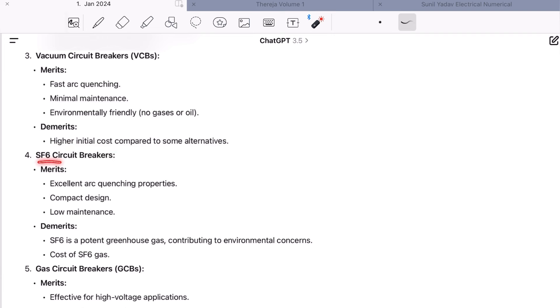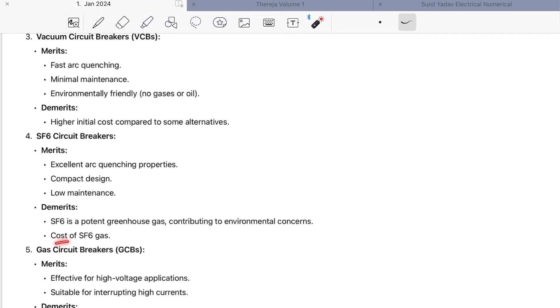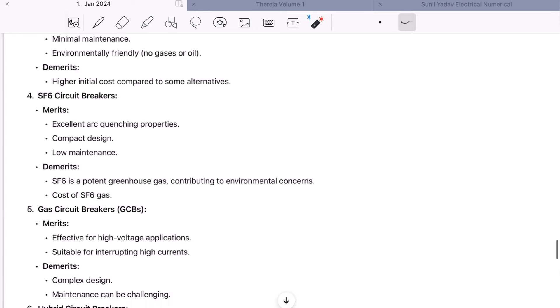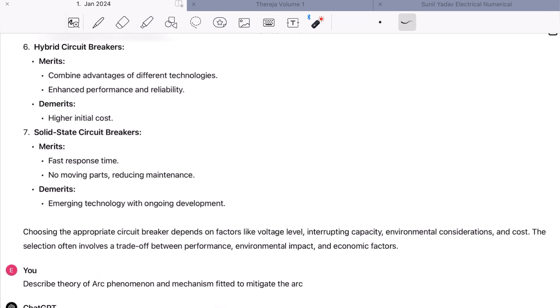Vacuum circuit breaker merits: fast arc quenching, minimum maintenance, and environmentally friendly — no gases or oils. Demerits: higher initial cost. The next type is SF6 circuit breaker. Merit: excellent arc quenching properties, compact design, and low maintenance. Demerits: it is a potent greenhouse gas contributing to environmental concerns, and the cost of SF6 is high. SF6 circuit breakers are also not used in the marine field due to their pollution-creating properties. Next is gas circuit breaker — merit: effective for high voltage application, suitable for interrupting high currents. Demerits: complex design, maintenance can be challenging. Other types include hybrid circuit breakers and solid state circuit breakers.